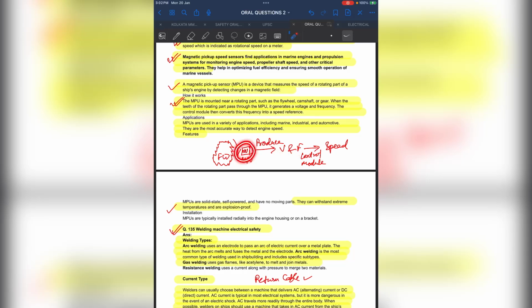Whenever this magnetic pickup sensor is fitted near the flywheel and the flywheel starts rotating, the flux changes, and due to this an EMF is induced. This induced EMF produces a voltage and frequency, and it is given to the control module. This voltage and frequency goes to the control module, which retrieves the speed of the flywheel or propulsion system.